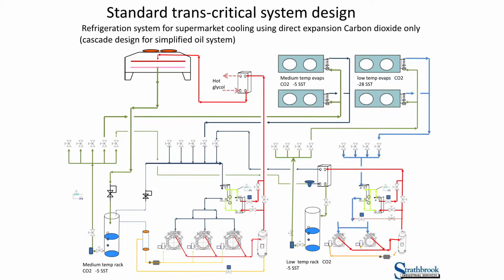So what we did was we took our standard cascade system, and if you can see over on the far side of the slide is the low temp, and on this side of the slide is the medium temp. All of the heat goes to the medium temp, goes up to the gas cooler and comes back down. That'll work in the cool weather, but in the hot weather, the energy efficiency will be half of what it is on a cool day.